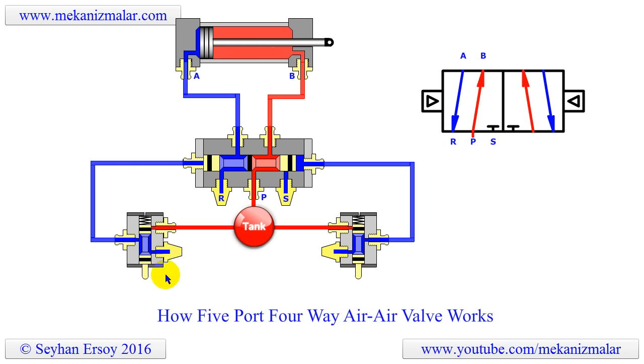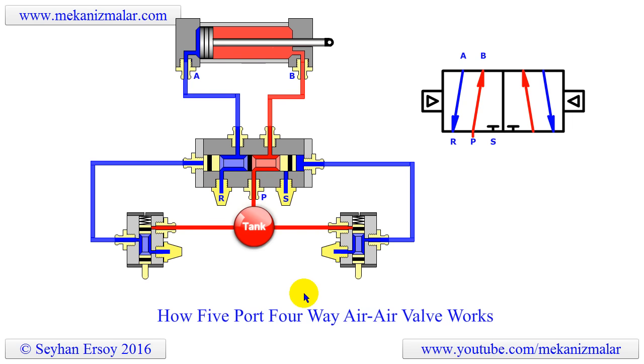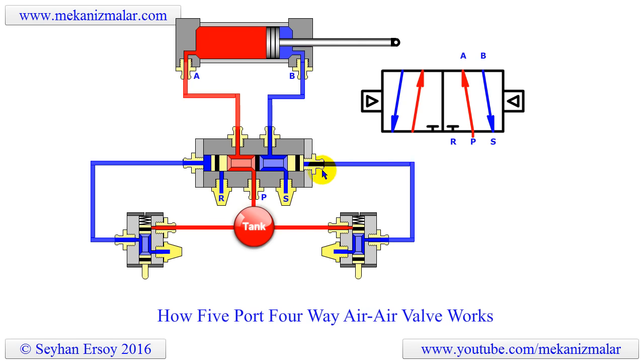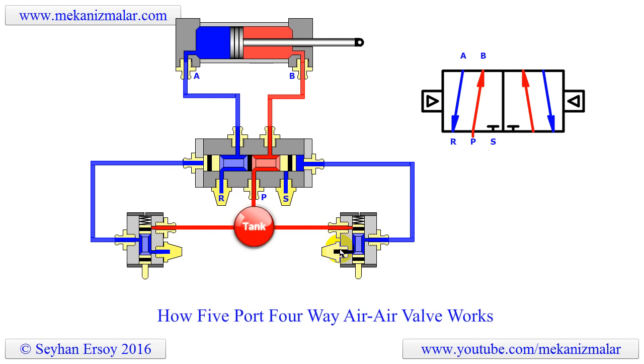Why is it also called air-to-air? The position of the spool is controlled by pilot air. Since both sides of the spool are controlled by pilot air, I called it air-to-air. The symbol changes positions to emulate the motion of the spool, and you can see the 4 ways the air flows, whether it is pressurized or at atmospheric condition.